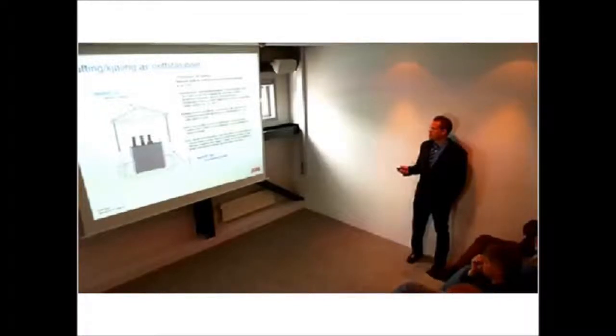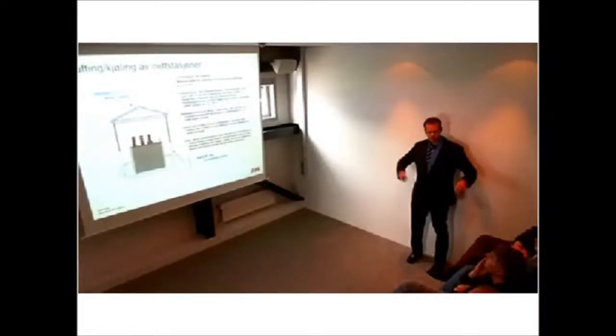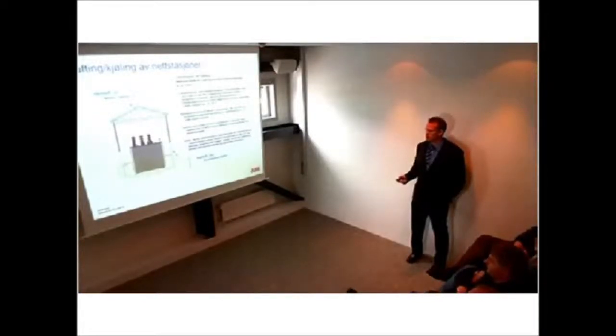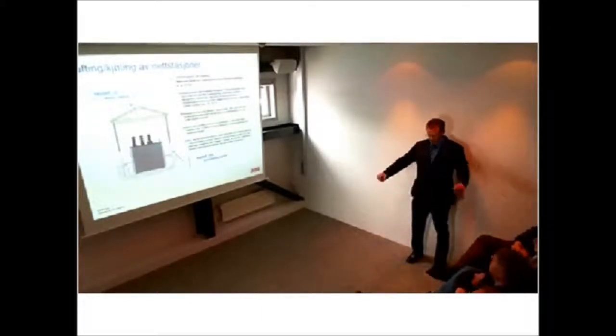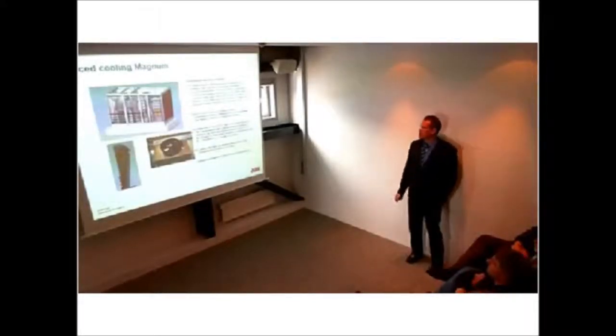That means a transformer with total loss, idle plus load loss, over 12 kW at 100% load will rise more than 55 degrees inside the substation, because the transformer will give heat to the walls, and the walls will reflect heat back. So it's not very good. We have some cases in Norway. In the winter time, when there's a lot of snow, the substation is all clean outside for 2 meters or something because of this. So we had to do something there, and then we had this forced cooling.